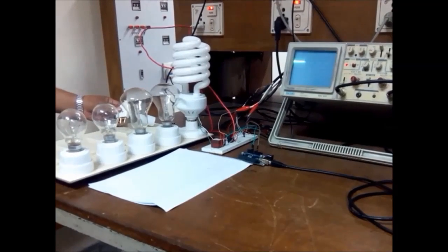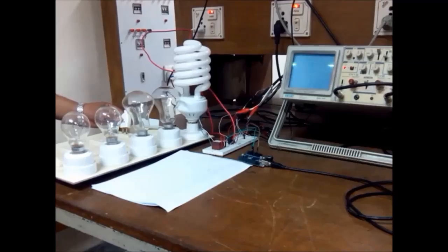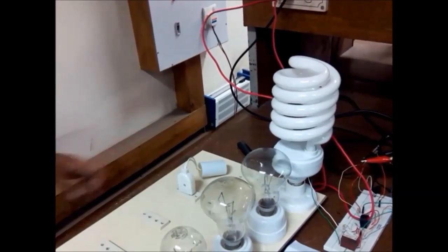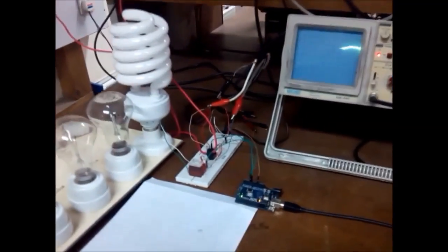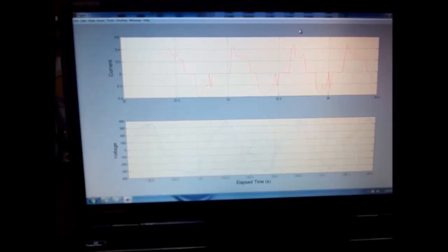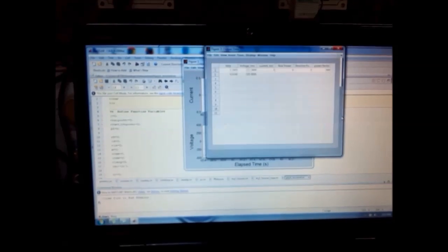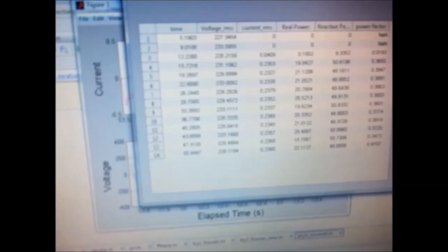In the demonstration, at first there is no load connected so there is no current in the wave shape. We then connect a capacitive load — a 3.5 microfarad capacitor bank. We observe the voltage and current waveforms: the lower part is the voltage shape and the upper part is the current shape. The power factor value updates every 5 seconds, and we can observe that the power factor is below 0.4, or around 0.4 sometimes.